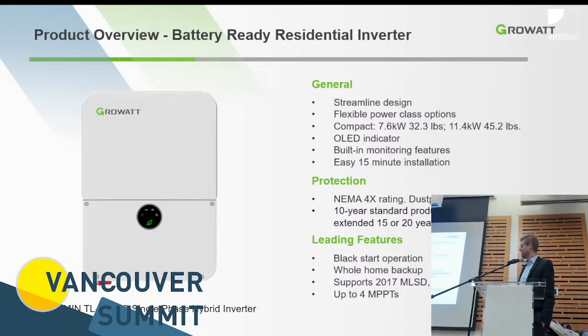As I mentioned, it has the SunSpec shutdown transmitter built in, AFCI is standard anyways, and for some units in the US, not for the Canadian units, there's also a revenue grade meter. We don't have that because Canada doesn't have any requirements for a specific measurement on the inverter itself. The 4 MPP trackers is a very flexible tool specifically for multi-orientation rooftops to design the system with as few components as possible. So just the rapid shutdown devices, ideally no optimizers, to really focus on as few components as possible in the entire system.